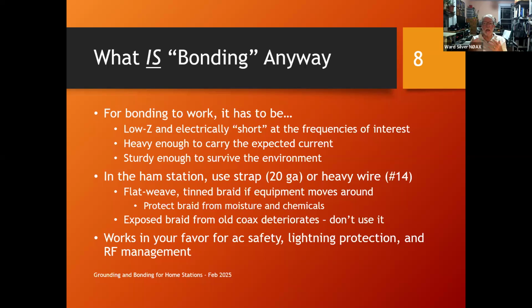If you don't have a heavy enough conductor and you damage it, you can cut it, and suddenly you haven't got a ground connection. If that conductor doesn't resist mechanical damage when you drive over it or whatever, you'll never know you've lost your ground connection. So these bonding connections have to be heavy enough mechanically to survive whatever the environment is.